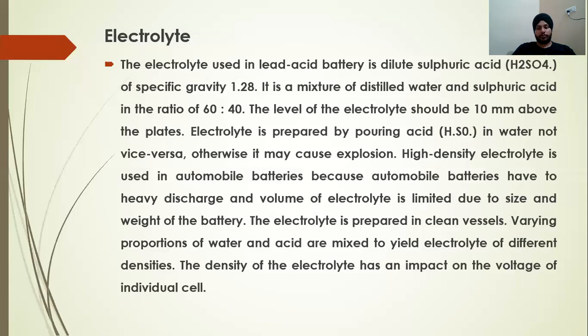The electrolyte is prepared by pouring sulfuric acid (H2SO4) into water — not the other way around — otherwise it may cause an explosion. High-density electrolyte is used in automobile batteries because automobile batteries need high discharge current and the volume of electrolyte is limited due to the size and weight of the battery. The electrolyte is prepared in a clean vessel with varying proportions of water and acid to yield different densities.